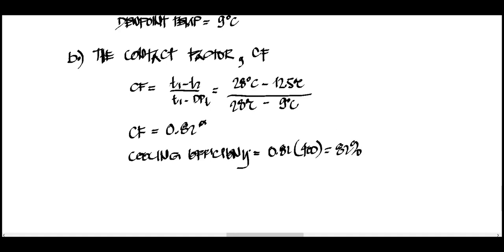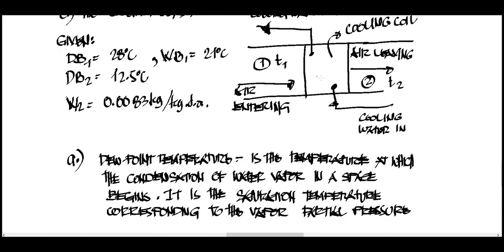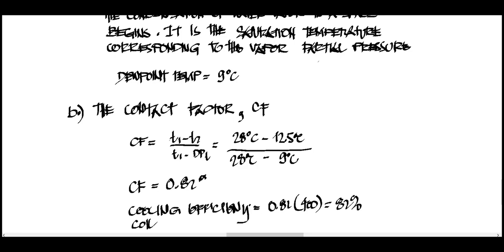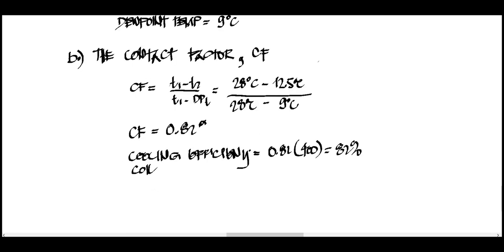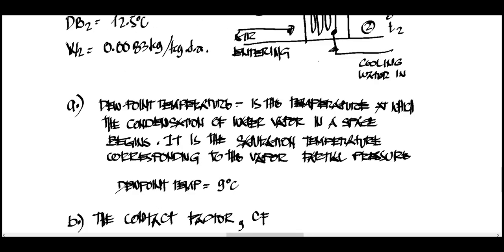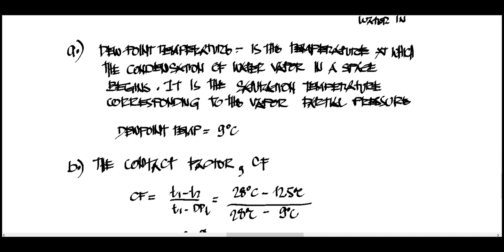Then we have 82% efficient yung cooling coil natin, cooling coil efficiency, sorry. So this determines how efficient our cooling coil is, which is this one, how the cooling coil here serves. So the contact factor determines the efficiency of the cooling coil by the change in temperatures.